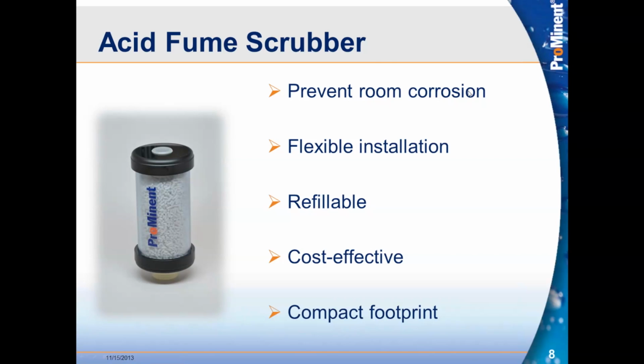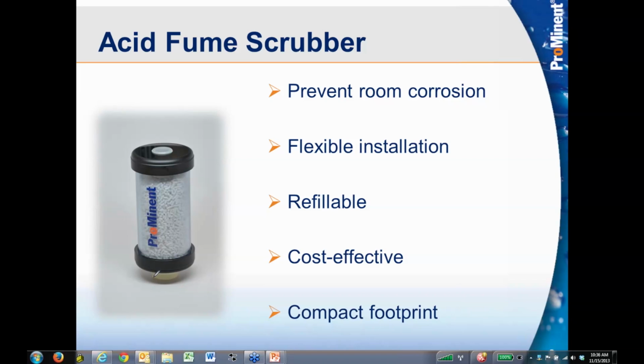So the way this works is that this is, and I'm going to pull out my little handy dandy drawing mechanism here. So down here, there could be a 3/4 inch nipple, and this will thread directly into a bung on a carboy. You could put a bulkhead fitting on here. There is a union that's supplied right here, 3/4 inch union. It allows us to break and remove the canister. So out of the tank, the fumes will come up through here, and then within these catalytic beads here, the fumes are neutralized. So we allow air in to vent, and any fumes escaping are neutralized in these beads.